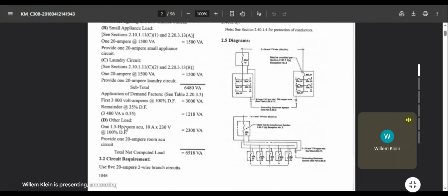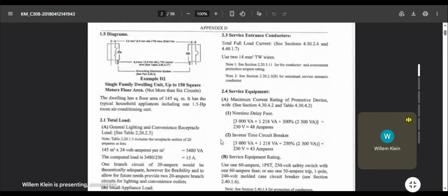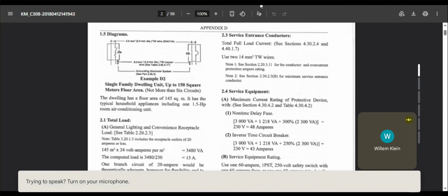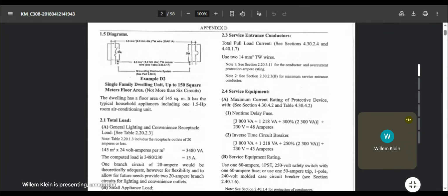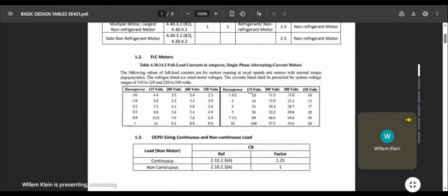Okay, and then after that, you will compute and add your other loads. When we say other loads, usually these are your individual branch circuits, meaning your motors, like for the air conditioning, or if you have a cooking range or other motor circuits. The important part here in your computation is the service entrance conductors, or your main supply, or your mains. For the total full load current, you can use section 4.30. I think you can use the reference in this table given to you for the horsepower of your motors, and also your circuit breaker or overcurrent protection device sizing for your motors. Okay.